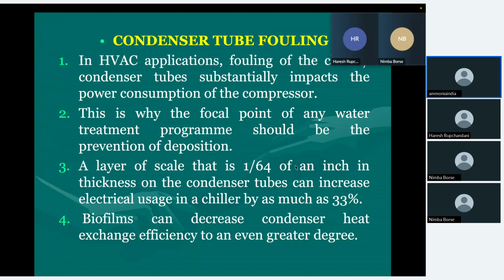A layer of scale of 1/64 inch in thickness on the condenser tube can increase the electrical usage in a chiller by as much as 33%. So you can imagine why we must take care of removing this fouling and cleaning the tubes. That is very essential. Cleaning of your cooling tower is also important. People don't drain the water, so what evaporates is distilled water, and in the tank the hardness starts increasing. So you need to drain an equal amount of water to what gets evaporated. Nobody does that. That is the most neglected component, the cooling tower, and as a result all that hardness goes into your condenser tubes and creates big problems.